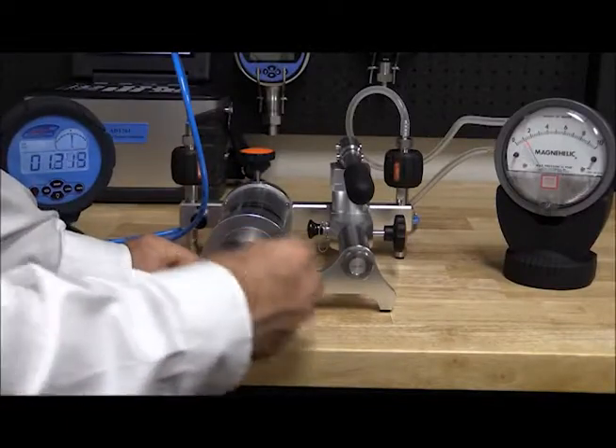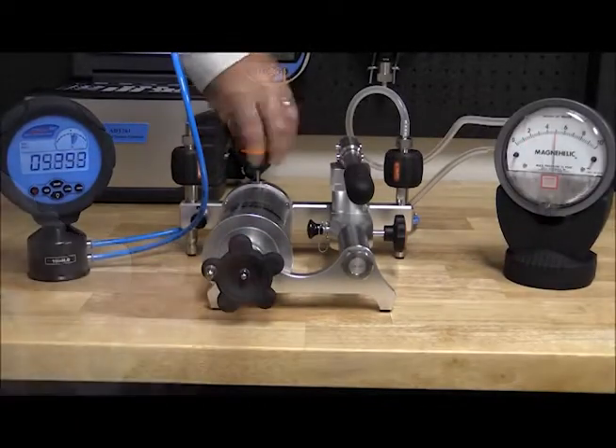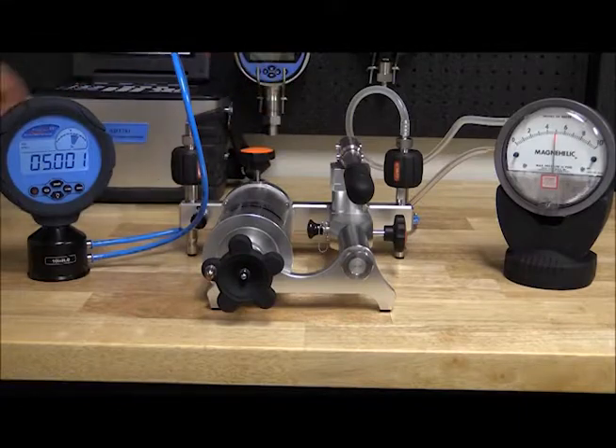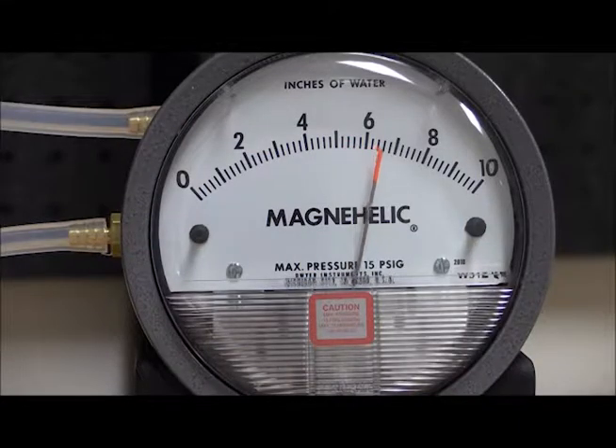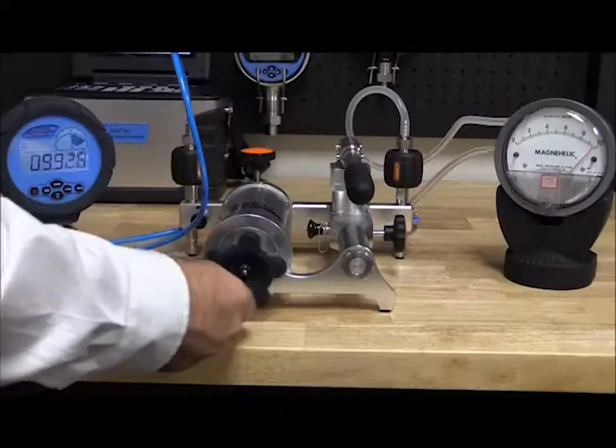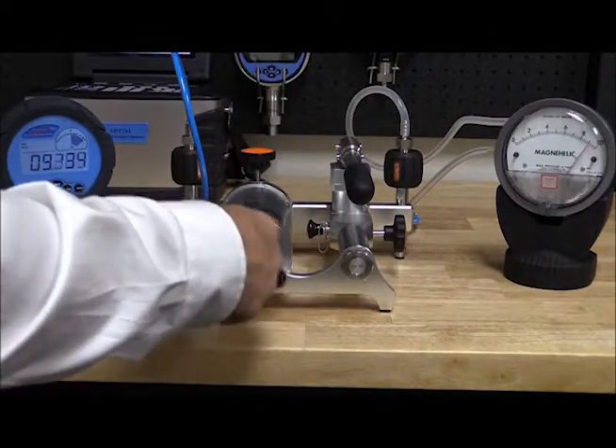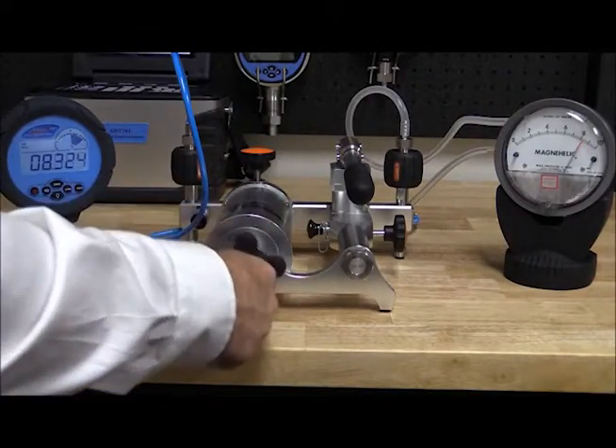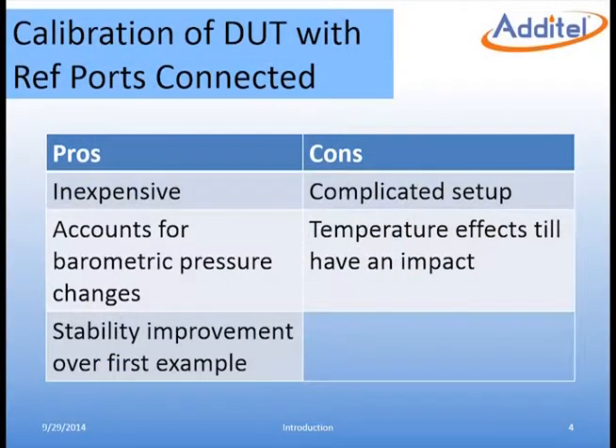Now we are ready to generate the pressure and record our results. Typically, 3 to 5 points are taken, both ascending and descending. By taking more than 2 points, we are able to check the gauge's linearity and hysteresis. In this method, the equipment is relatively inexpensive and does a much better job accounting for errors caused by changes in the environment. By having the low lines connected together, the measurement is more stable at each point. This setup is more complicated than the first example.